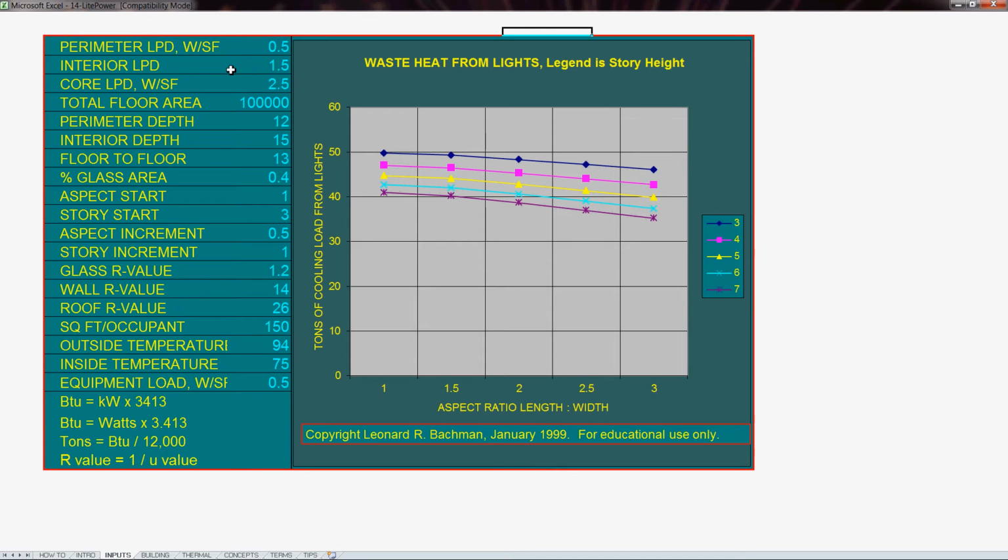And in this scheme, which is similar to figure 14.3 in MEB, we look at lighting as being supplementary to daylight, so we need less closer to the daylight source at the perimeter of the building where the windows are. So defining the building in 3 zones as perimeter, interior, and core, we can assign preliminary estimations of lighting power just to see what the repercussions of these kind of decisions and targets are.